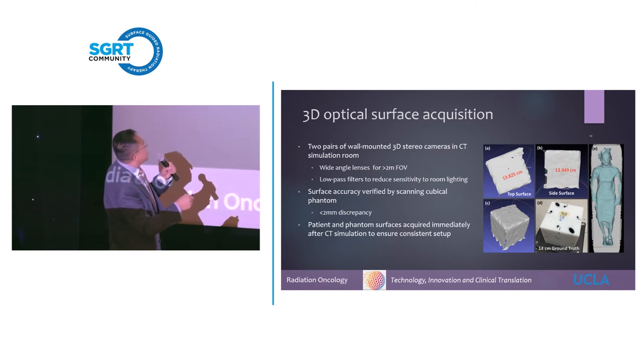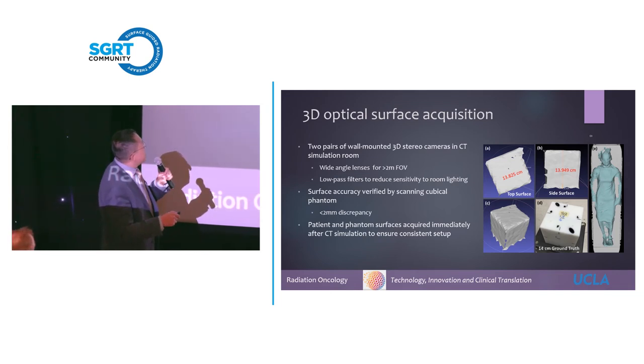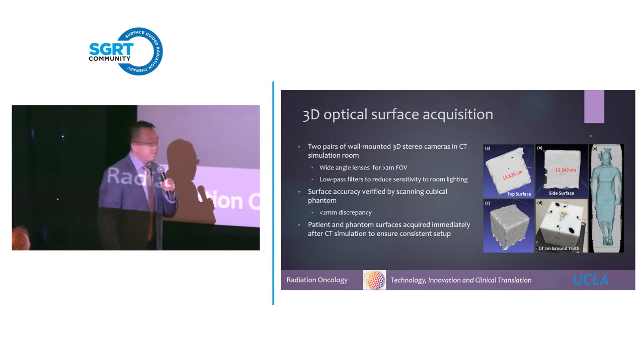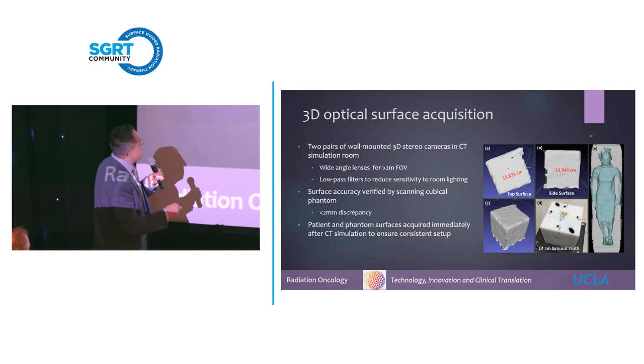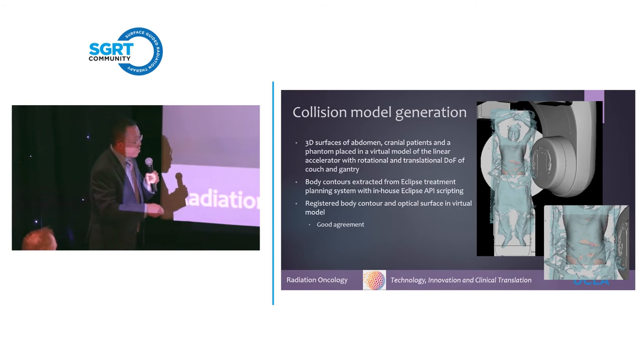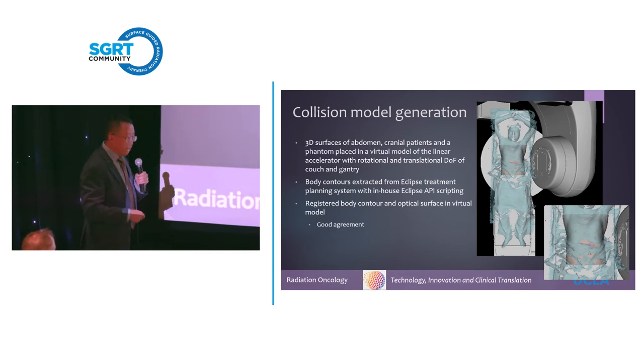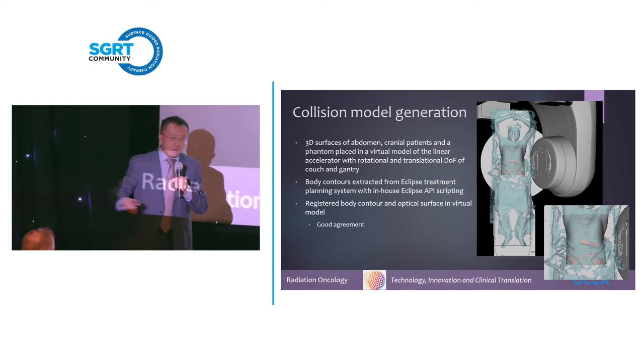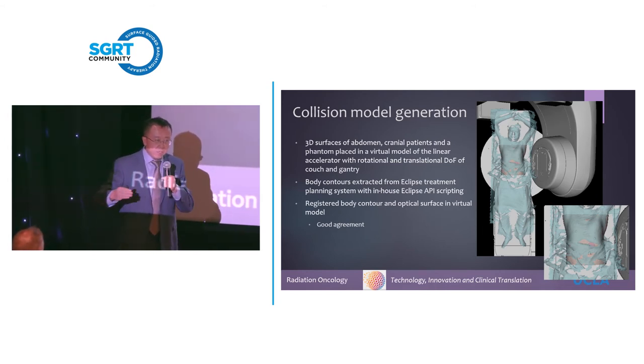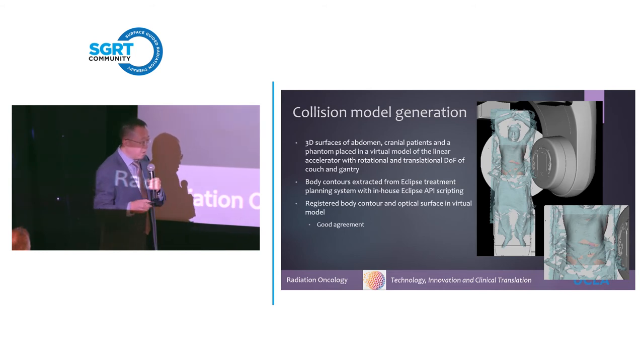We installed two pairs of wall-mounted 3D cameras in the CT simulation room. Both cameras are equipped with wide-angle lenses for over 2 meters of field of view and low-pass filters to reduce sensitivity to room lighting. We verify the surface accuracy by placing a phantom of known geometry across the field of view, confirming that surface image error is under 2 millimeters. For the patient, we acquire the surface image immediately before or after the CT scan, so there is very minimal motion between the optical and CT imaging.